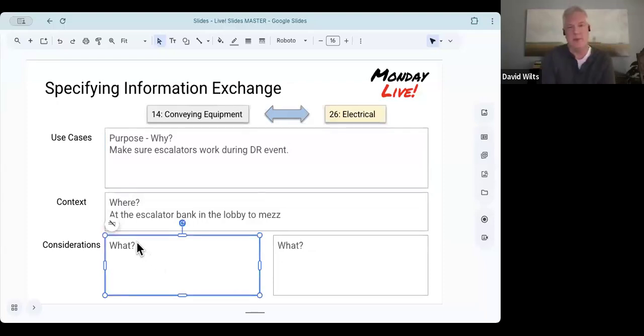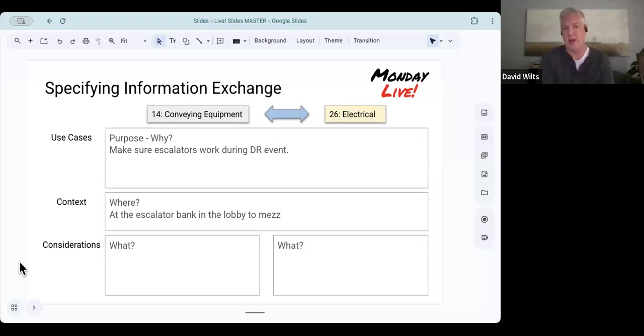Unfortunately, none of that would come from the Division 14 spec and be relayed to the electrical contractor, not from my experience. Usually deciding which lifts are going to be operating during a blackout and run on generator power is something that falls through the cracks. This is obviously why we're talking about this stuff. This is where the lift provider would need to indicate, if the lift provider even knew or even talked about it, which of the 6 lifts are going to stay powered up from generator power.